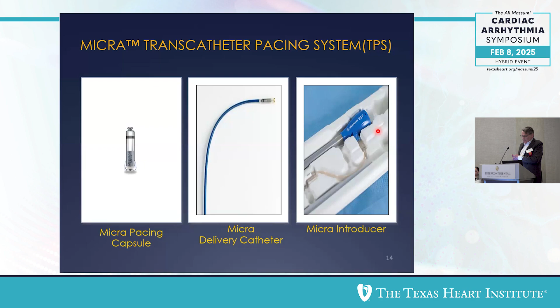All right, so the system itself is composed, obviously, of the pacemaker, the delivery system, and the introducer sheath. The delivery catheter is 105 centimeters. It's a pretty simple system. It's got a deflectable tip, and then you deliver it by releasing the capsule, and it's tethered at the end, so you can recapture it and reposition it.